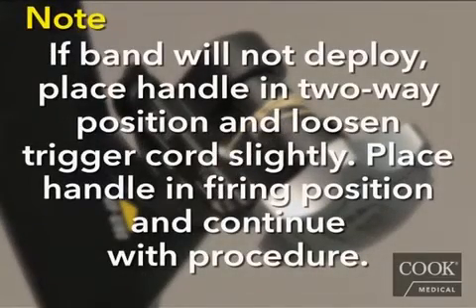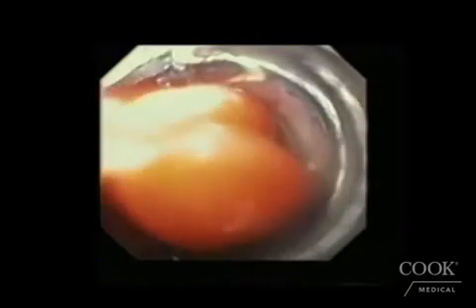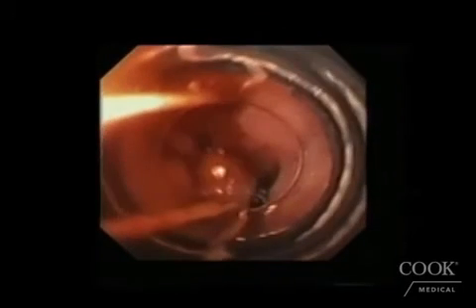Note: if band will not deploy, place handle in the two-way position and loosen the trigger cord slightly. Place the handle in the firing position and continue with the procedure. Release the suction button of the endoscope. Insufflate air, then withdraw the scope slightly to release the ligated varix.